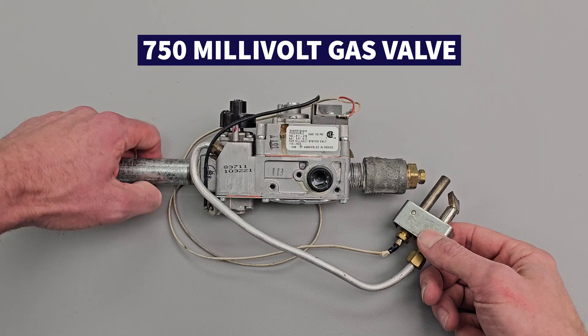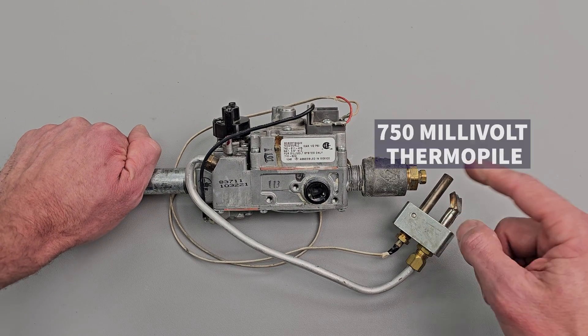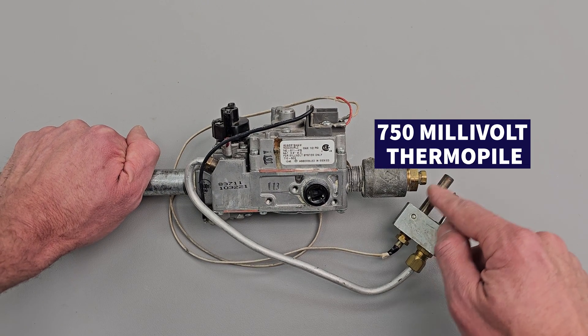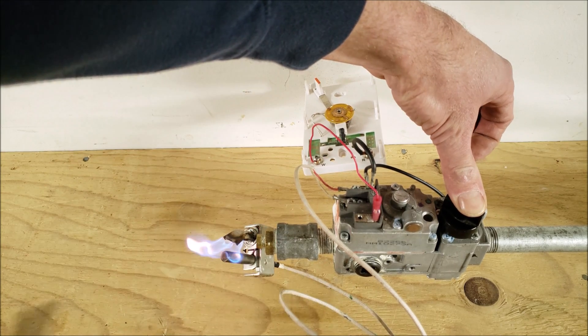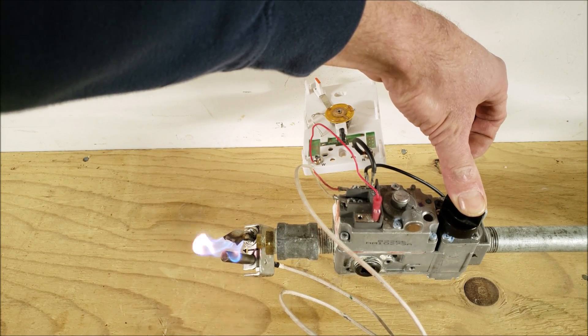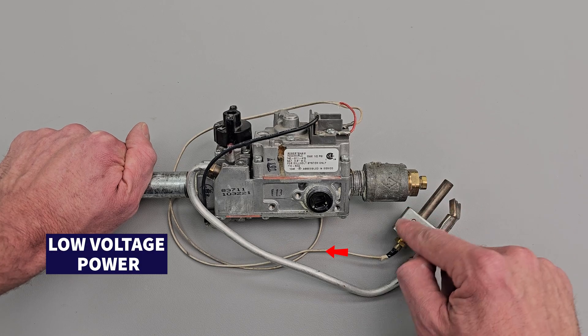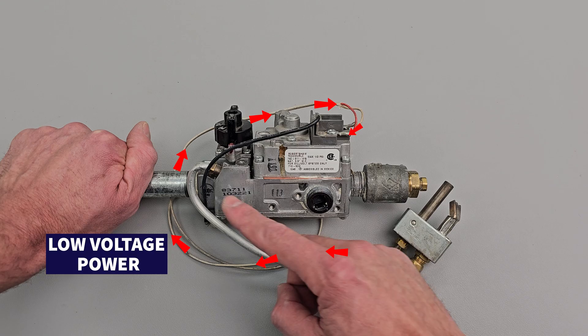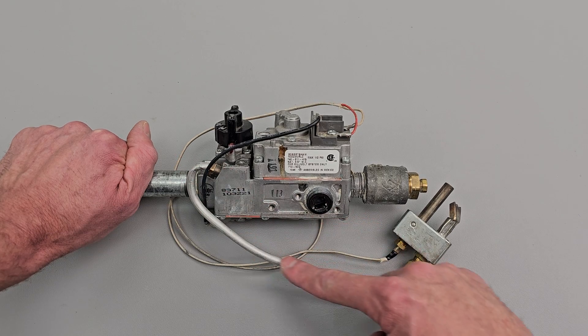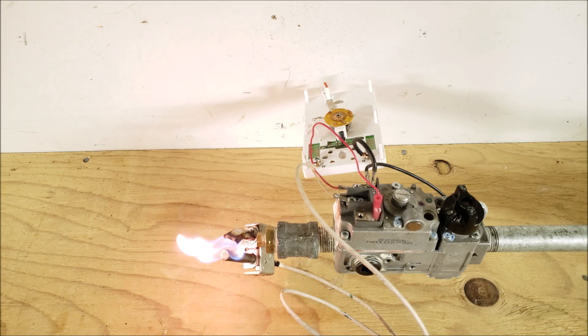Here we have an example of a 750 millivolt gas valve with a 750 millivolt thermopile. If you manually light this by pressing this button down and putting a flame right here, that flame is going to envelop the thermopile. When this is heated, it's going to apply low voltage power over to the gas valve, which is going to keep this pilot solenoid open, so you'll have this standing pilot remaining lit.